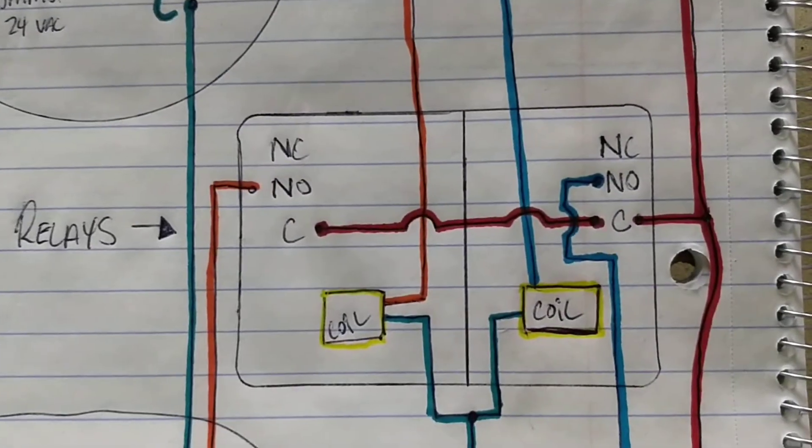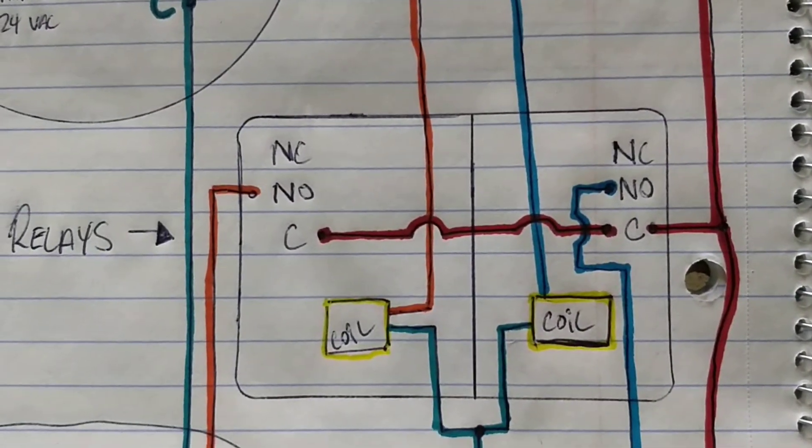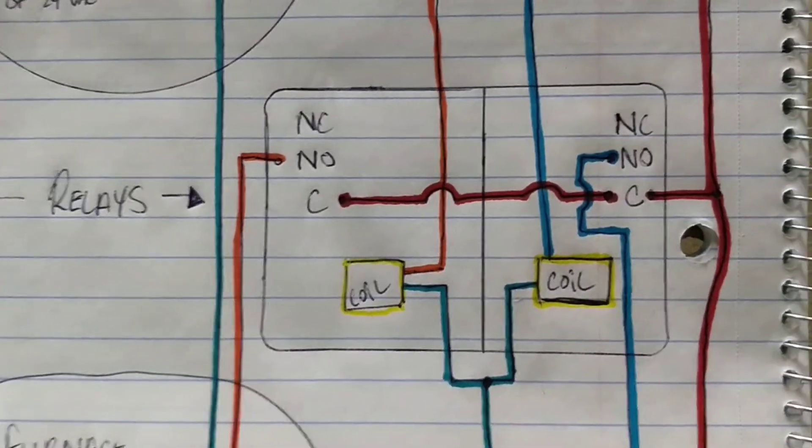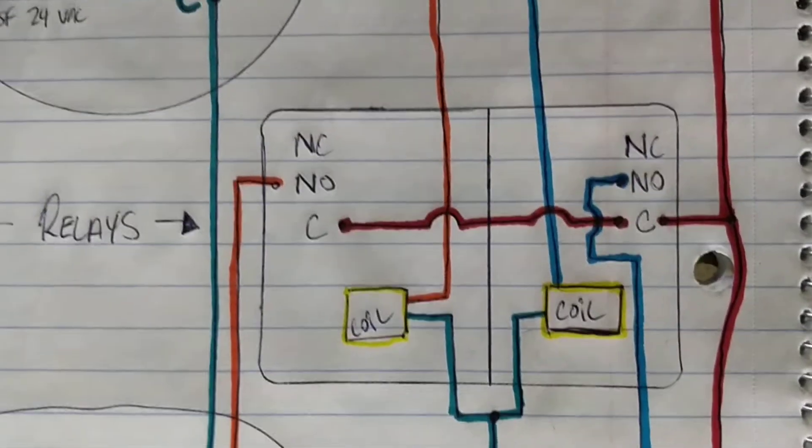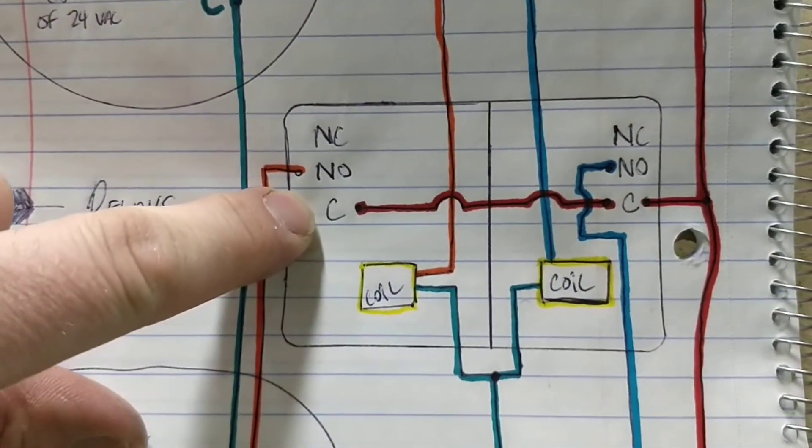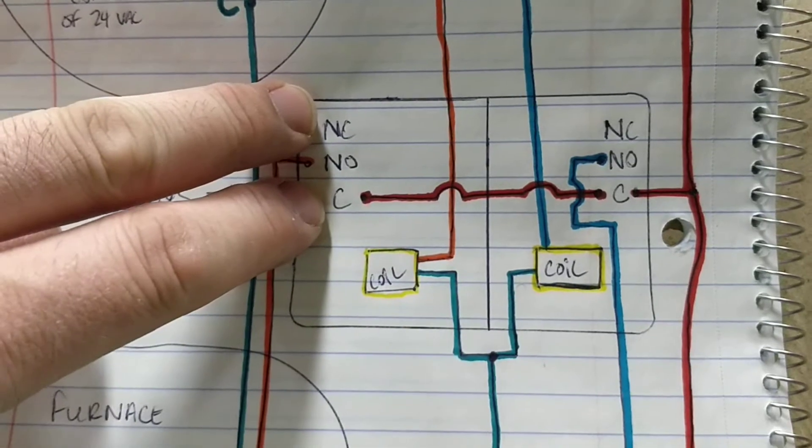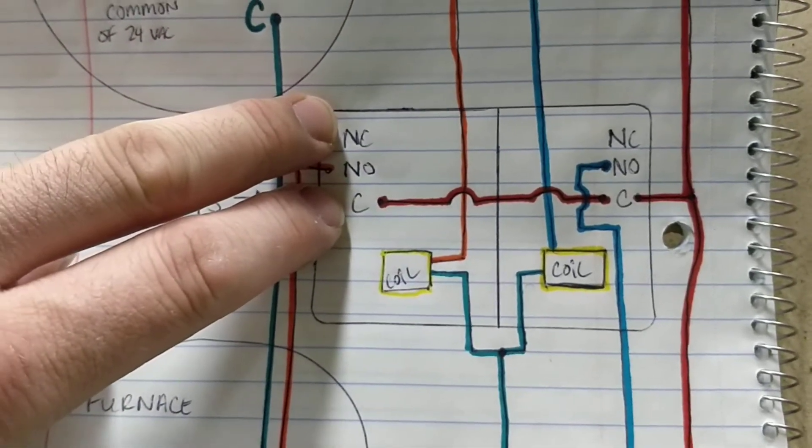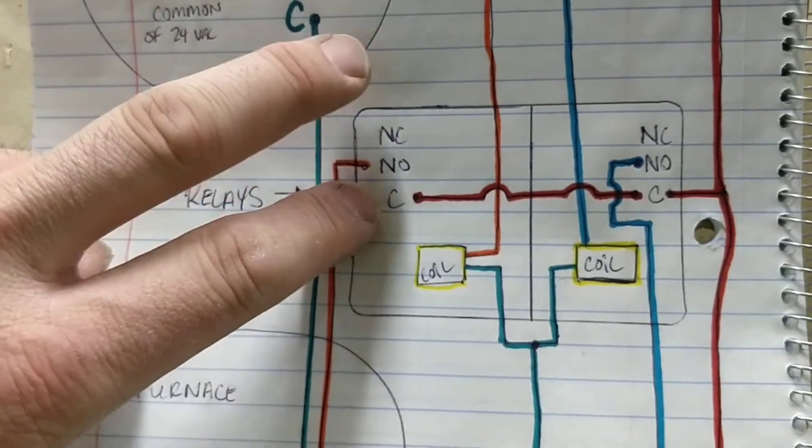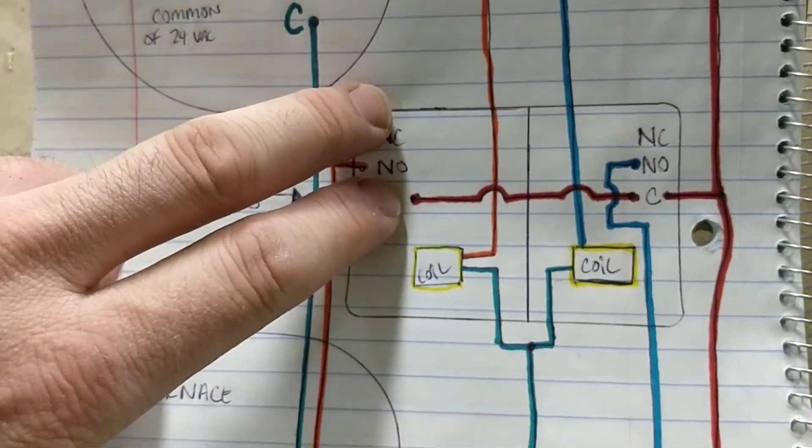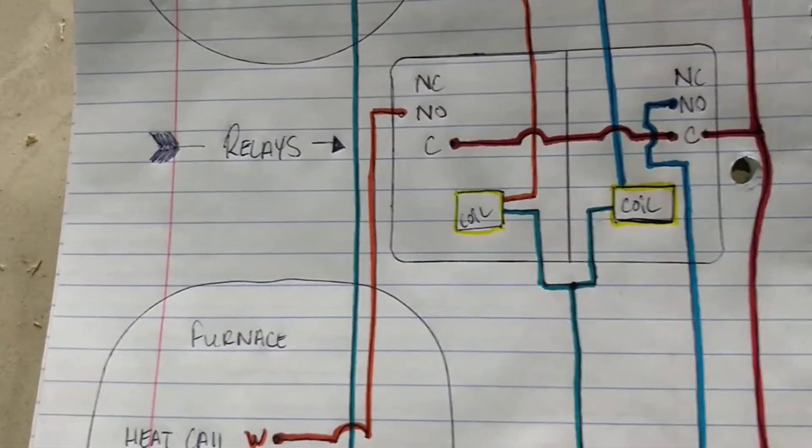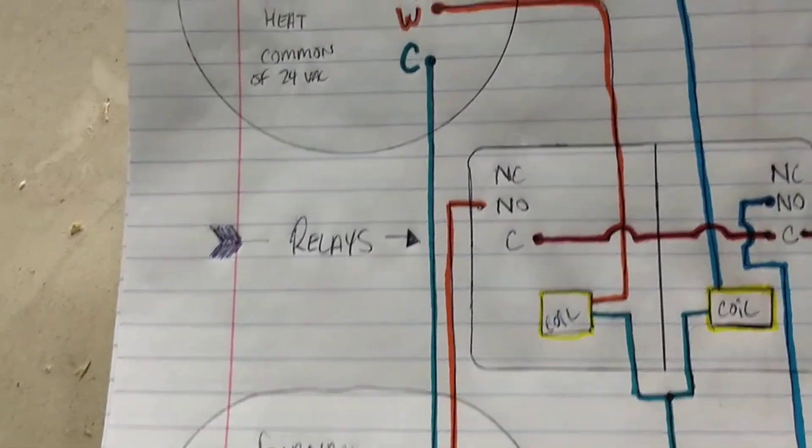The idea with the relays, your terminals are the common and the normally open, because the normally open and the common will make contact once the relay energizes. So the normally closed, which is this guy and that guy, if you were to put a meter on or check them, or if you hook up your connections to your furnace and they immediately turn on, you probably have this one and this one hooked up instead of this one and this one. So, you've been warned, I can't fix stupid and I can't help you if you're too stupid for yourself.